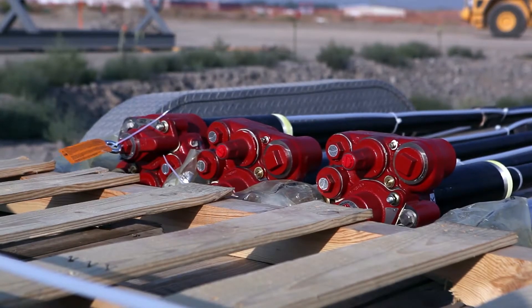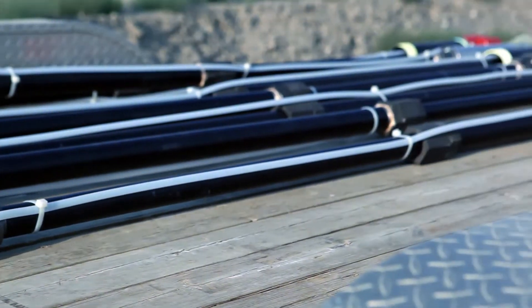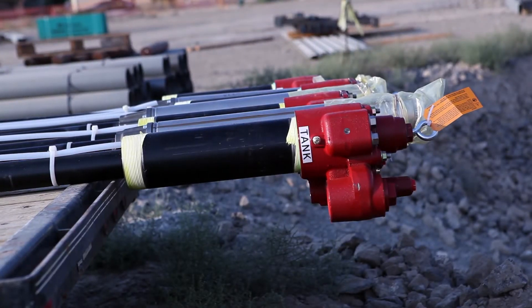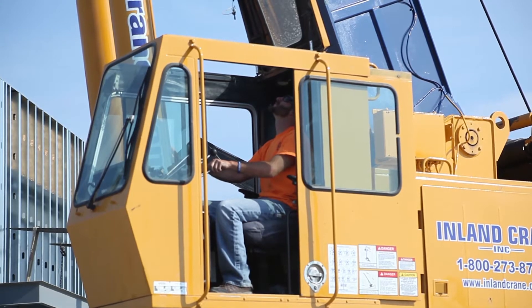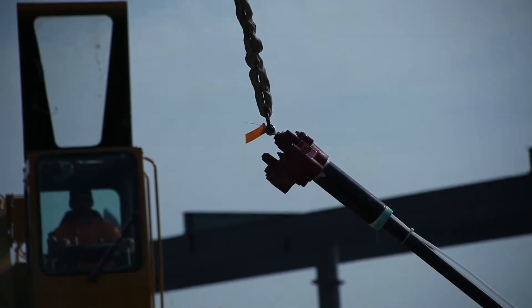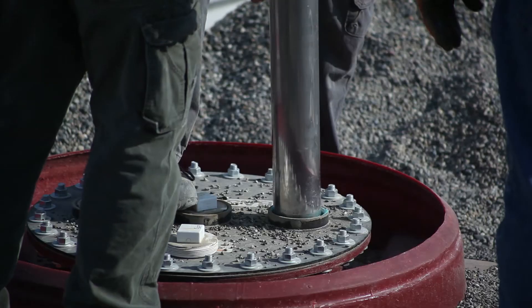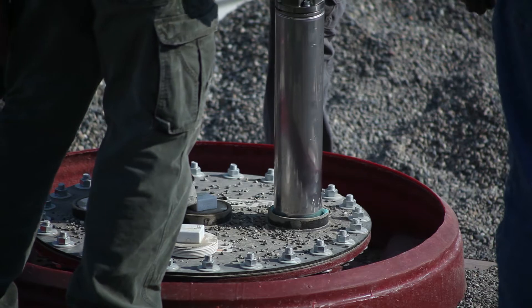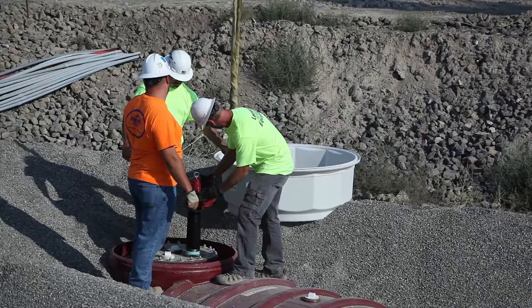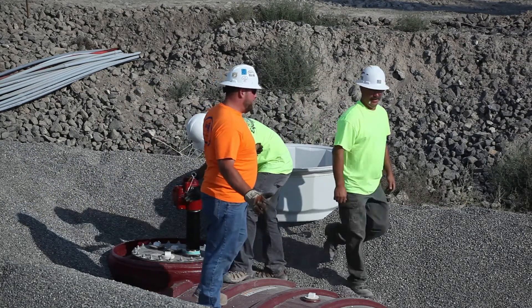Because of this site's unique configuration with extended volumes across the pipes, it drove us very quickly into the two-horsepower product range. We did not think this customer wanted to step up into a six-inch pump — our very high-flow pumping option — because of the different installation and maintenance techniques required. This keeps them in the traditional four-inch line while ensuring they'll have plenty of flow for their site.